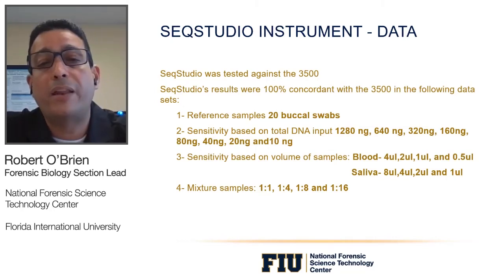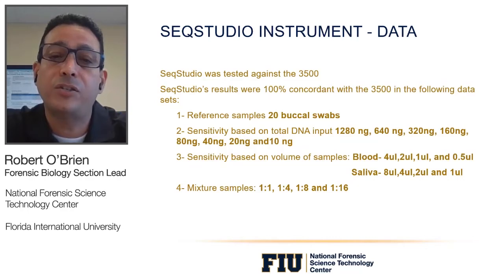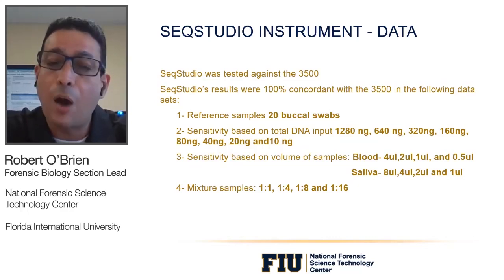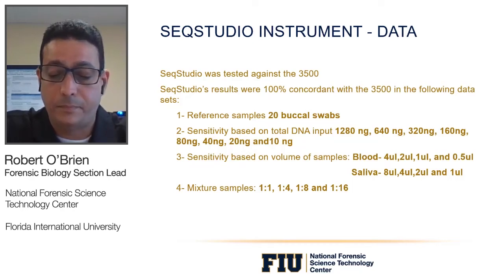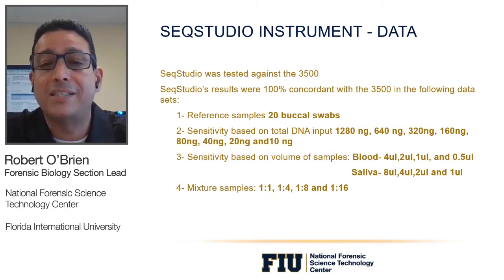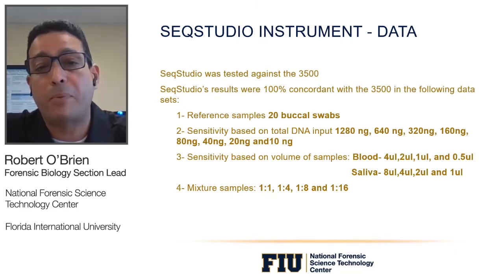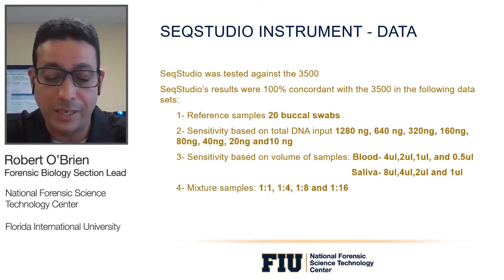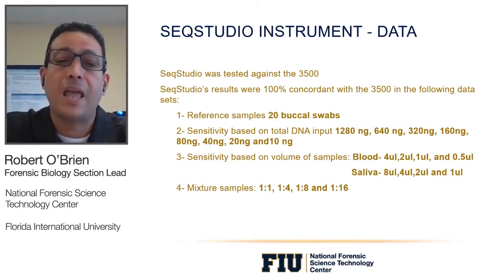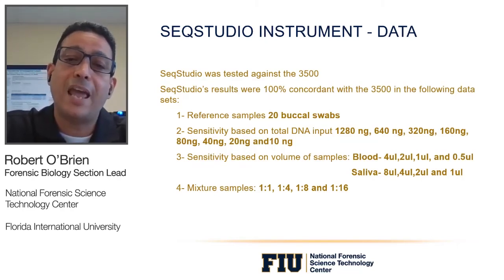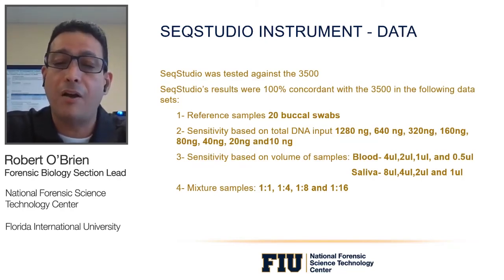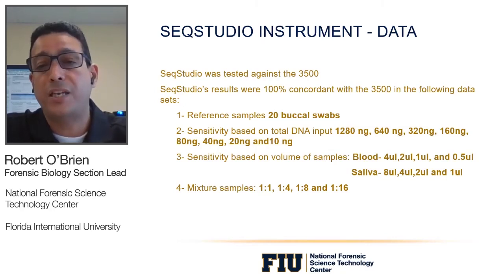It is important to note that we ran the same plate on both the SeqStudio and the 3500, and obtained 100% concordance. The one difference for data analysis is that the SeqStudio requires GeneMapper IDX version 1.6. This also demonstrates that implementation of a SeqStudio does not in any way affect the quality of the data you will get.